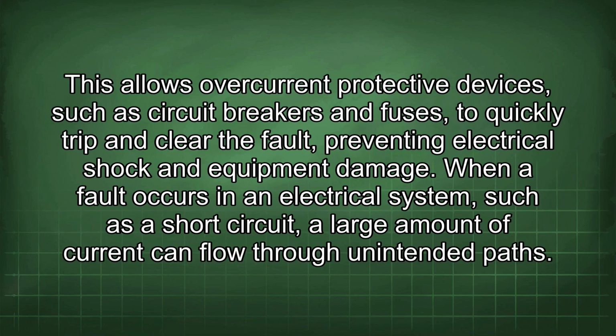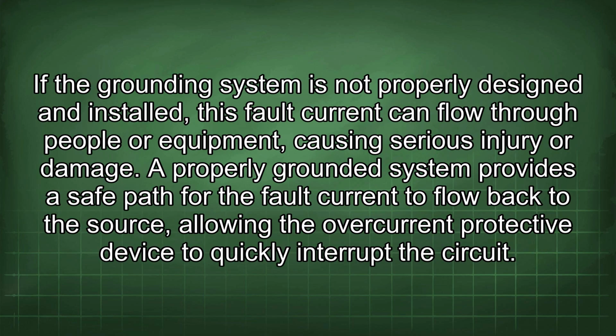This allows overcurrent protective devices such as circuit breakers and fuses to quickly trip and clear the fault, preventing electrical shock and equipment damage. When a fault occurs in an electrical system, such as a short circuit, a large amount of current can flow through unintended paths. If the grounding system is not properly designed and installed, this fault current can flow through people or equipment, causing serious injury or damage. A properly grounded system provides a safe path for the fault current to flow back to the source, allowing the overcurrent protective device to quickly interrupt the circuit.